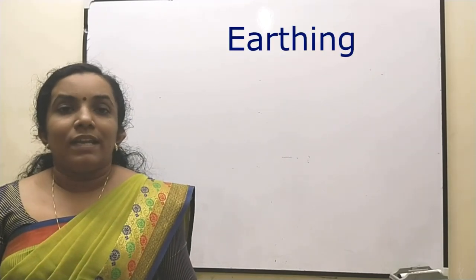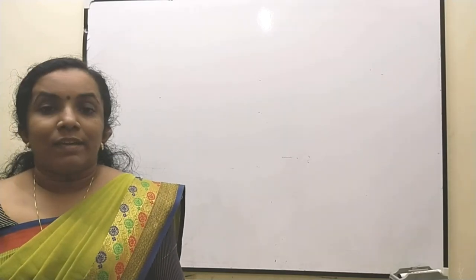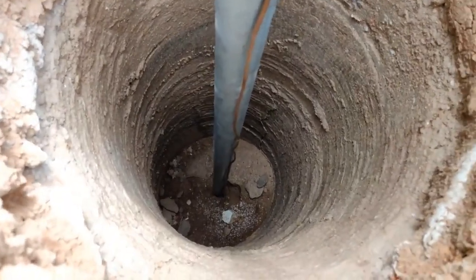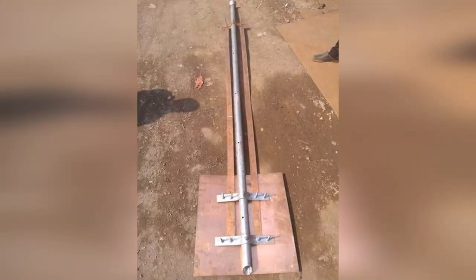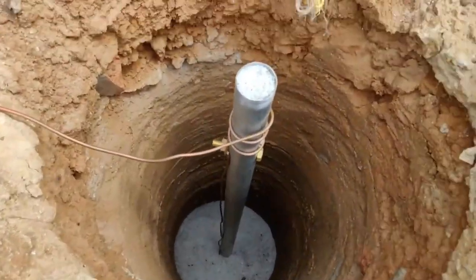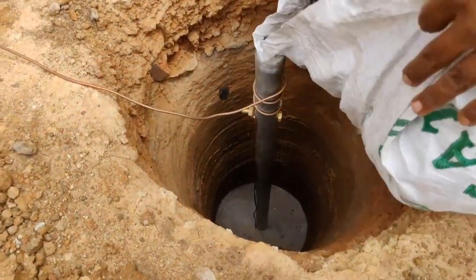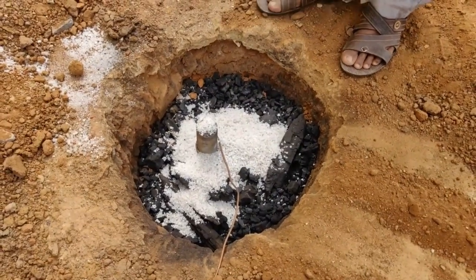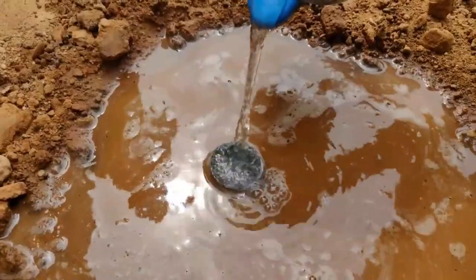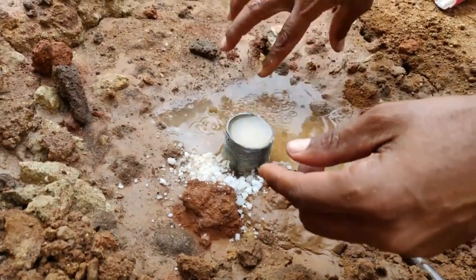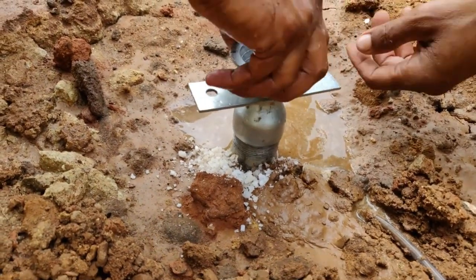Earthing is of two types: local earthing and earthing for the appliance. For local earthing, a hole about two to three meters deep is dug in the ground. A copper rod covered by a hollow insulating pipe is inserted, and a thick copper plate of 50 × 50 cm is welded at the lower end. The plate is surrounded by a mixture of charcoal and salt, which makes good contact with the earth. Water is poured through the pipe periodically to keep the ground damp and ensure proper conduction.